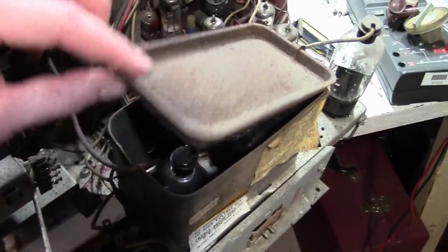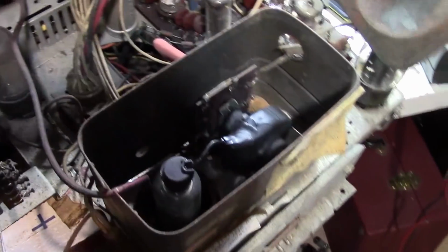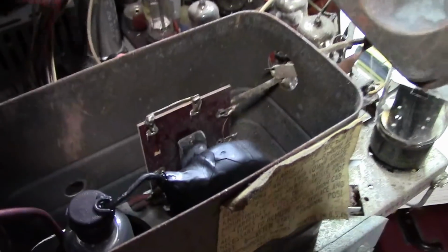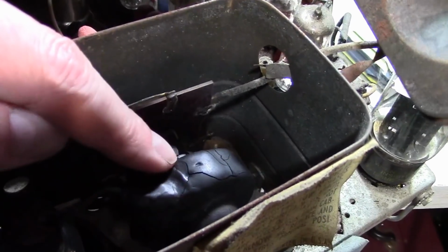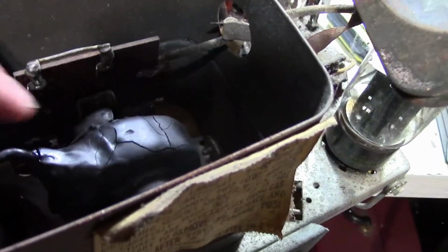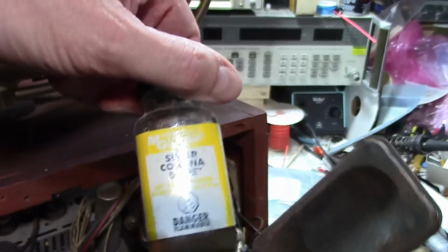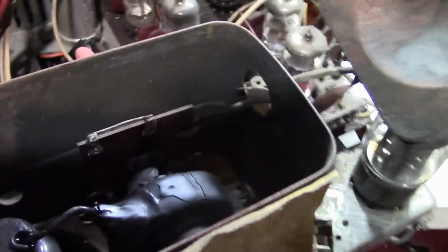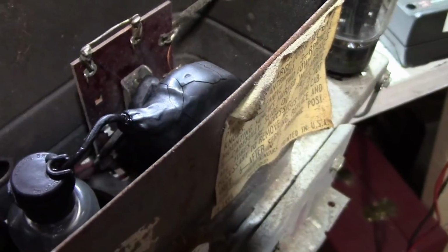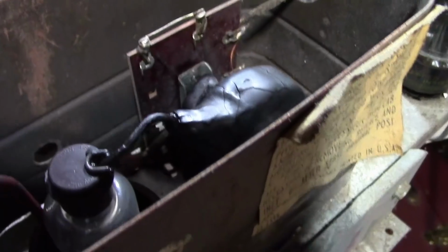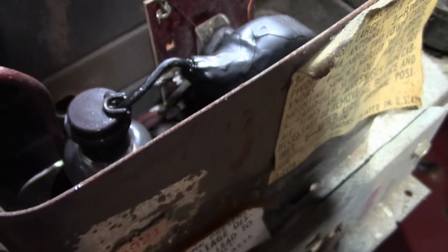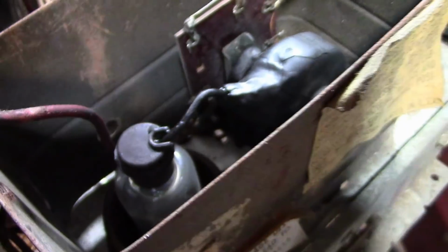Just had to pop the cover off the high voltage box. Now you can see down inside there, and it looks fine. Very often the coating on these is cracked - it's no big deal, throw a little Corona dope on there. This high voltage sealant will be just fine. It doesn't mean they're melted or fried or anything like that, it's just age cracks the coating on them. And this, I think somebody just didn't know how to do it.